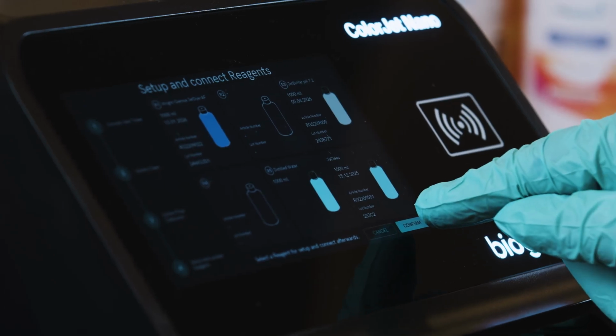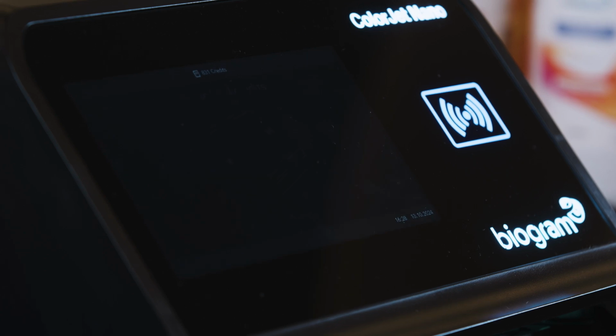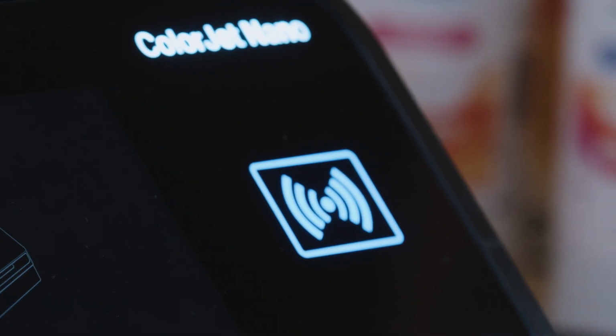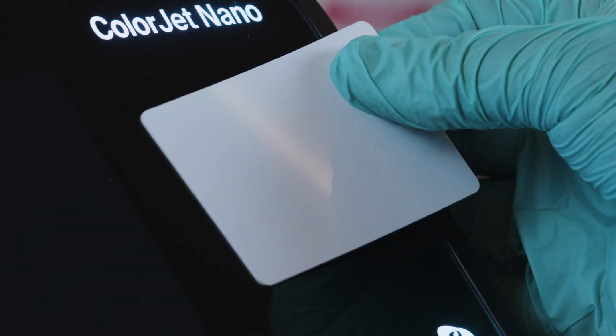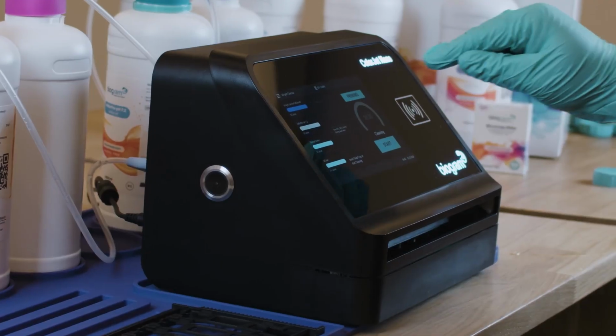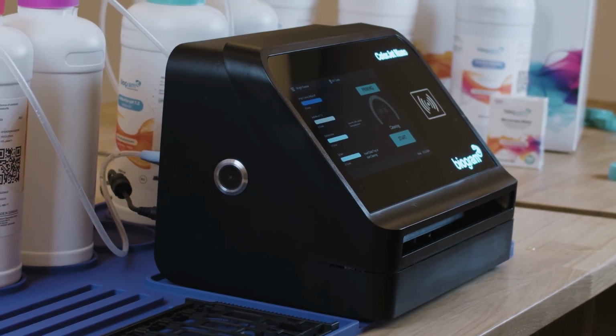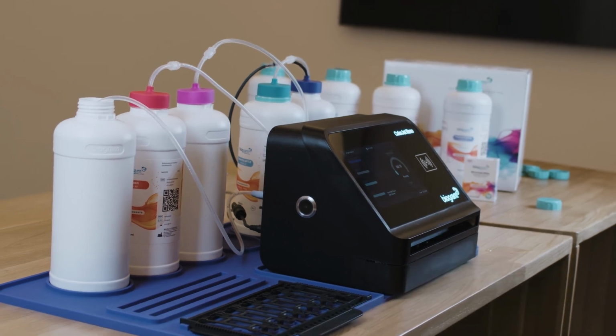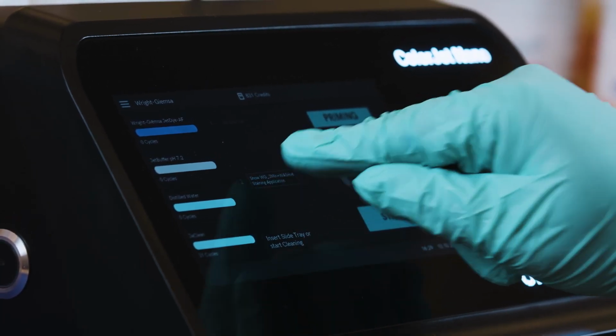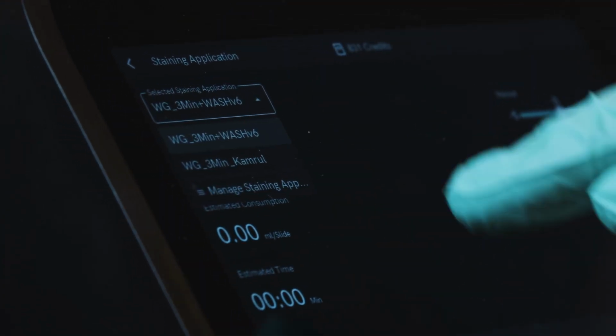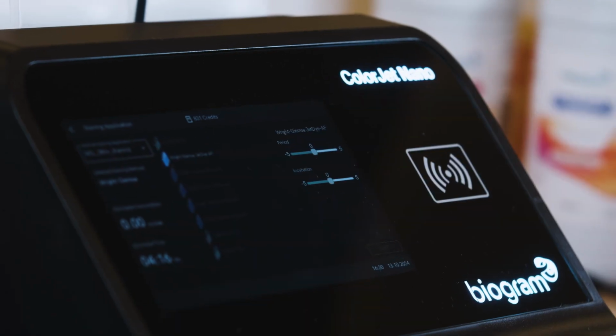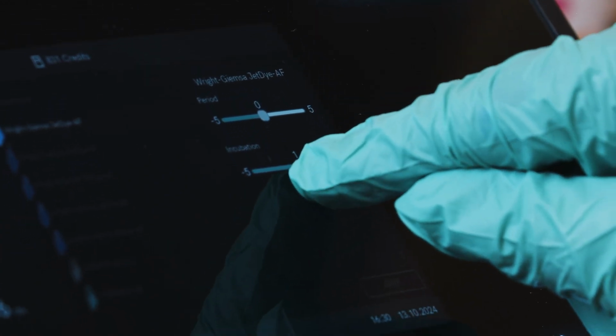To activate the system, load the credits by holding the credits card included in the system kit near the NFC symbol on the display. Next, press Prime to fill the tubes with reagent. Ensure that each reagent is fully drawn into the system. Choose your preferred staining application. You can adjust the incubation time to customize the staining outcome.